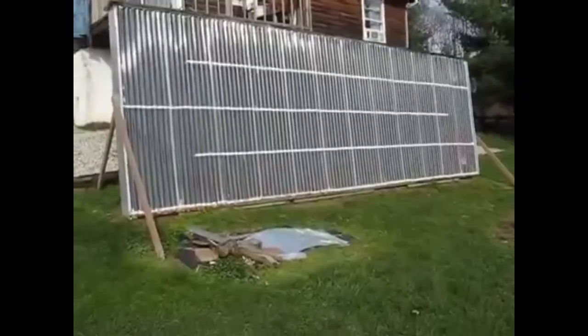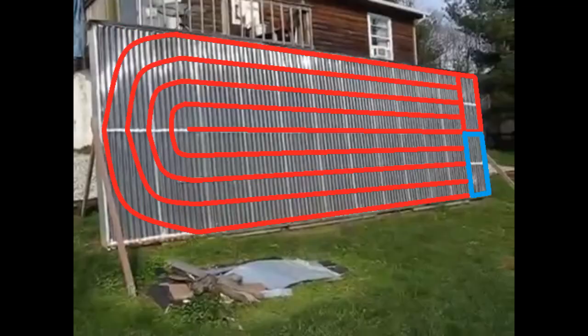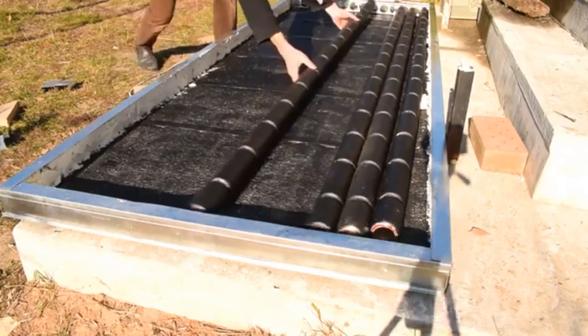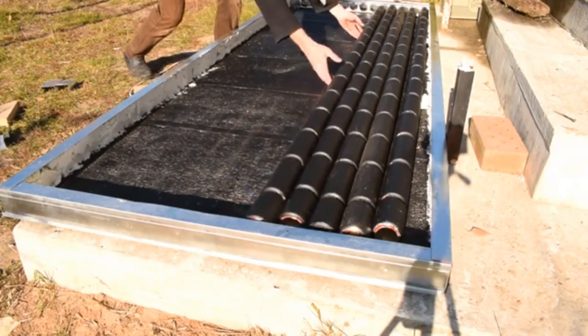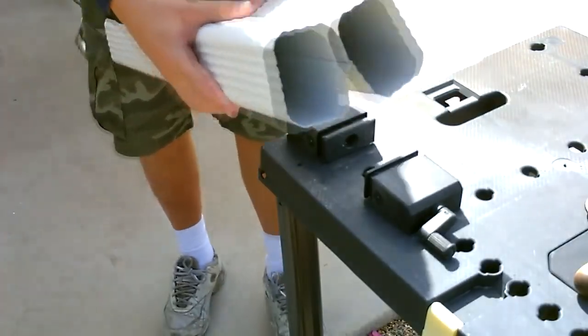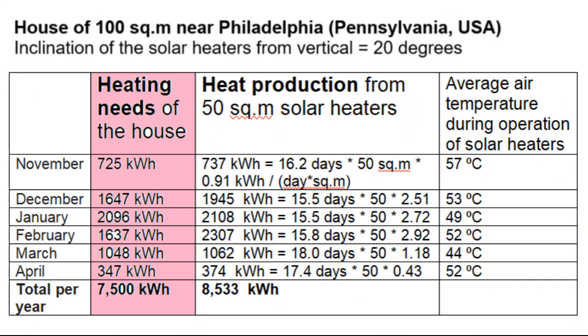The pipes for the solar heaters can be installed horizontally, so that half of the pipes directs air to one side and the air returns through the other half. However, pipes with a diameter of less than 15 cm will have too much resistance to air movement and therefore require vertical placement. We use three fans, but thermostats can turn off one or two fans if the temperature difference between the pipes is less than 20 degrees. Thanks to this, the fans annually consume 150 kWh of electricity, which is approximately 20 times less than if the thermal energy in the house were produced by air source heat pumps.